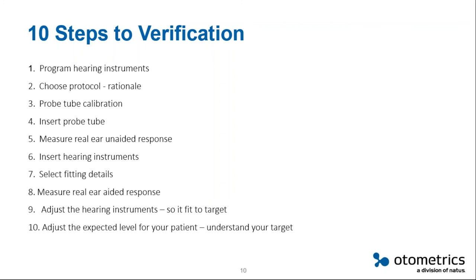Then we need to choose a protocol — finding out the goal and the rationale we are going to use for this fitting. You can use NAL or DSL, or you can also use targets from the hearing aid manufacturers. Then you need to do a probe calibration, and then insert the probe tube. That's the part people are a little bit afraid of. Then we measure the real ear unaided response. Together, inserting the probe tube and measuring the REUR will give us the safety that we are doing a good job by placing the probe.